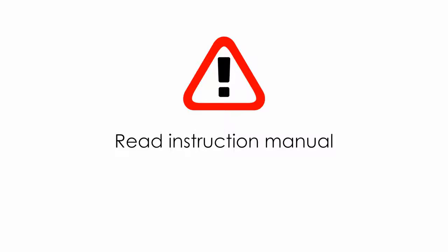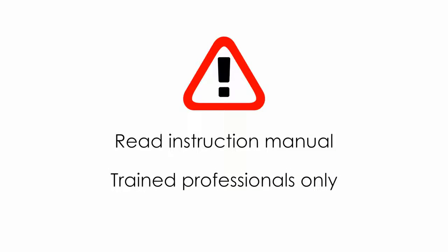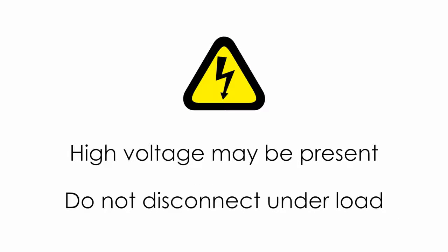Before installing any Tigo products, please read all instructions and safety information. Installation must be performed by trained professionals only. Always use the proper tools and safety equipment and adhere to all national and local electrical codes. Never disconnect components while under load. All Tigo components are shipped in the on position, therefore always assume high voltage is present.